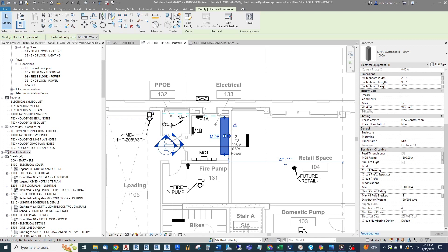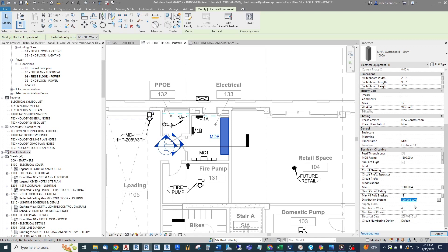Down here at maximum number of single pole breakers — this gets a little tricky in Revit — it's going to show individual feeds on this switchboard that represent three-pole feeds typically. So this means we can have six three-pole breakers in here, which should be enough for now; we can change this if needed. Very important is which distribution system is set. Right now the only one available in this project is 120/208, so it is set properly. If we had 480, that would appear as well.